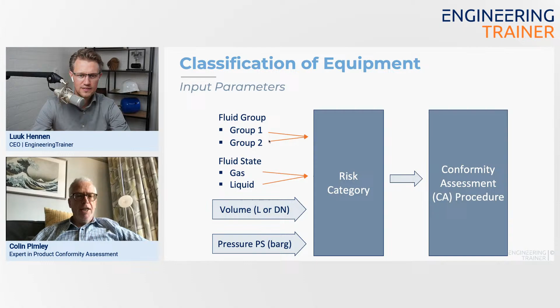Let me jump to one of the tables that we have available as well, Colin. This one, as hopefully everyone can see, is one of the 9 tables in the PED. This one is for pressure vessels which contain what we call a Group 1 gas, sometimes referred to as the more hazardous type of fluids. On the vertical axis you've got the pressure PS in bar, and across the horizontal a measure of the volume of your pressure vessel in liters.